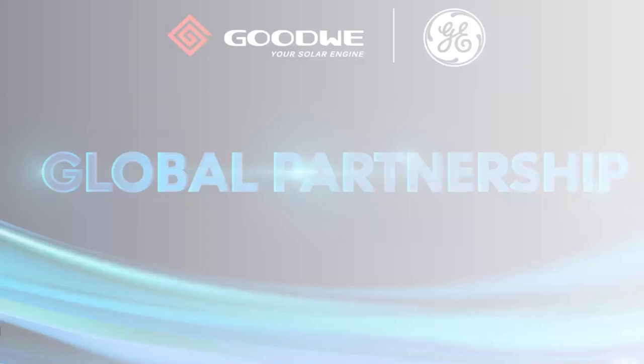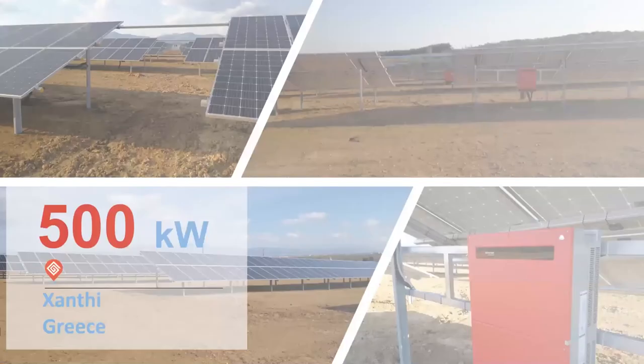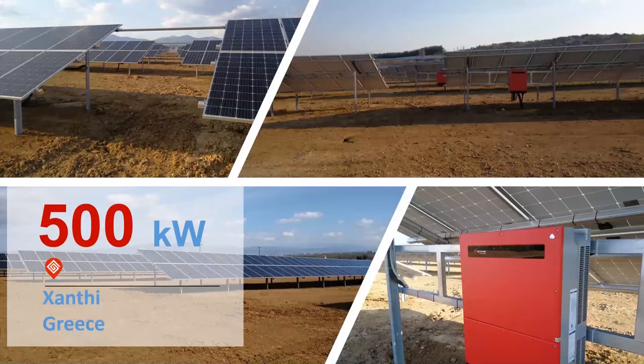So, just for your information, these are the pictures of one of the first installations of 500 kilowatt we have done in Greece. Mr. Pavlidis is supporting the maintenance on this plant. So if you are interested, you can ask him, and I can anticipate that the results are quite amazing, I have to be honest. You see here, the decision of the installer was to put the inverters just below the PV panels. And this is totally okay because the degree of insulation and protection of our devices is IP65. So you can make this kind of installation without any problem.